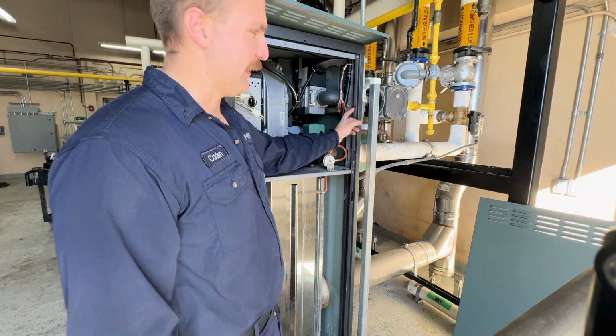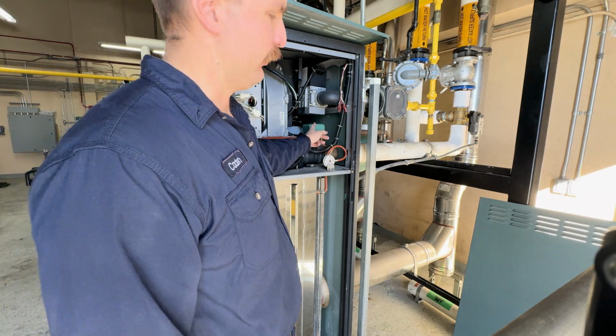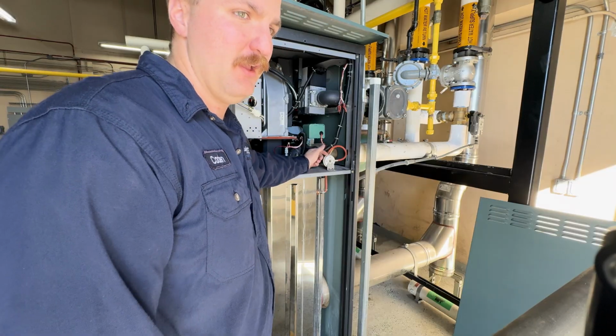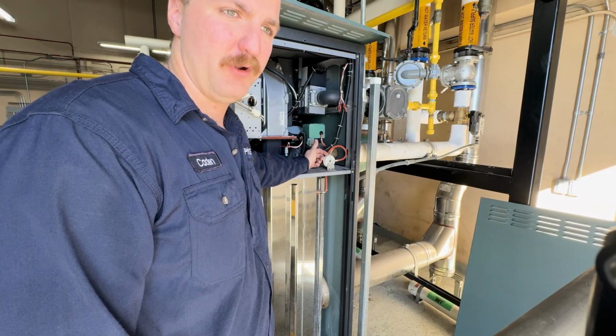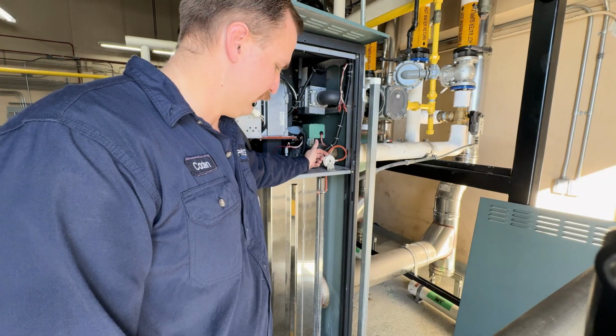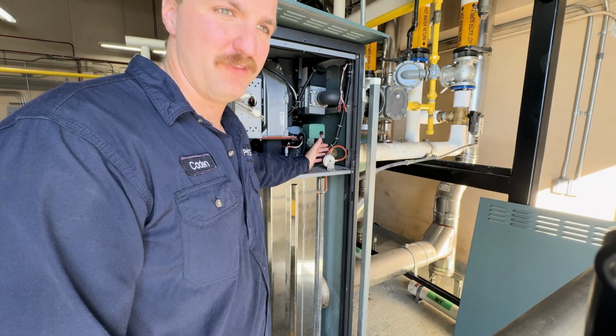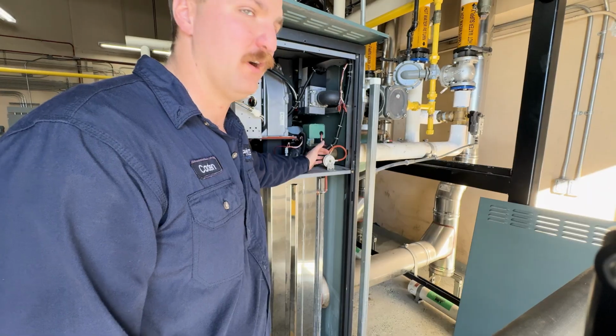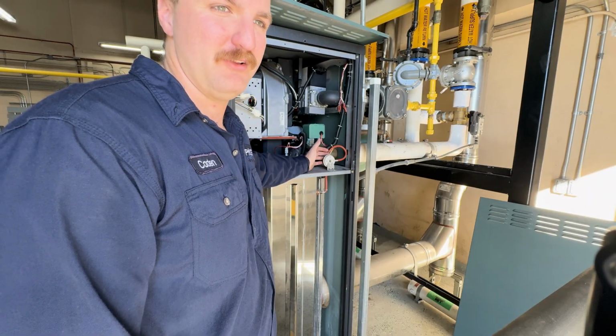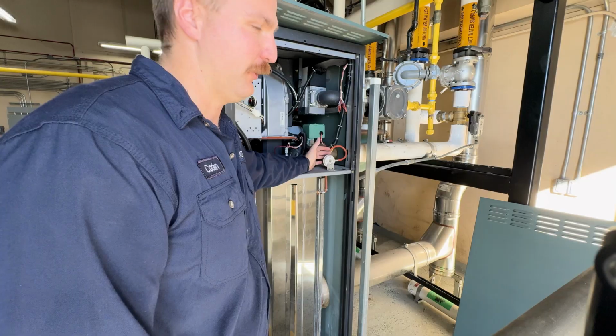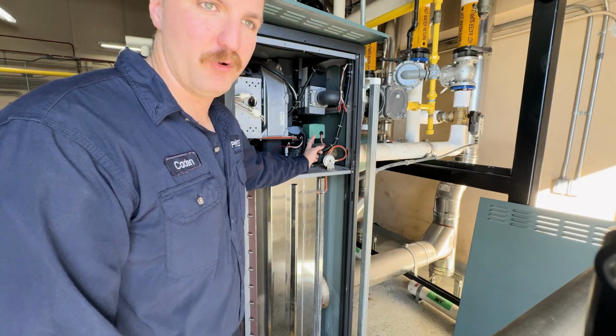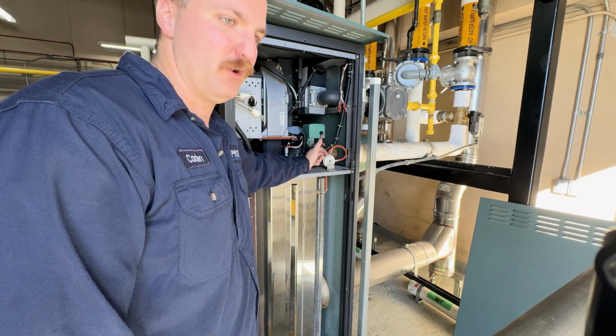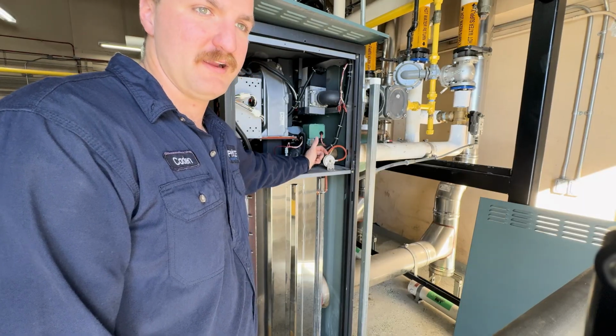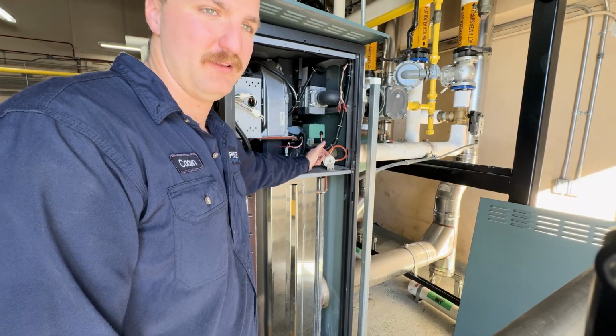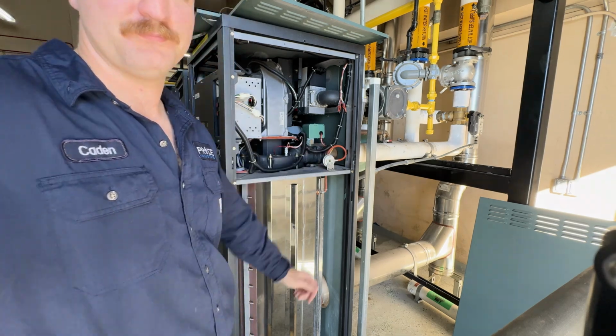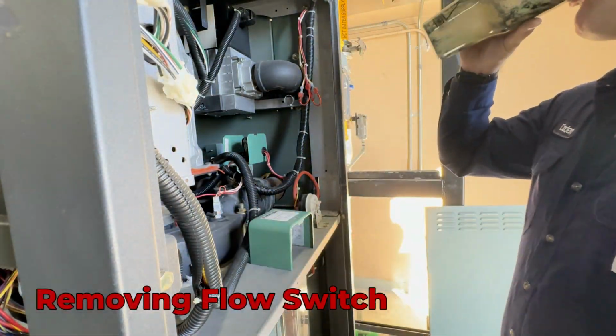All right, so what's going on right now is this flow switch right here on the boiler is leaking from the fitting on the bottom. We spent about 10 minutes tearing the boilers apart over here trying to find where that leak is coming from. Thankfully, it's not a cracked heat exchanger. That's an expensive and in-depth repair. Honestly, at this point, if it was a cracked heat exchanger, the best bet would just be replace the whole boiler. Thankfully, we have a parts boiler over in the corner that has a spare one of these switches. So what we're gonna do is isolate this boiler, lock out, tag out, remove the switch, put a new one in, and hope that it doesn't leak. There we go.